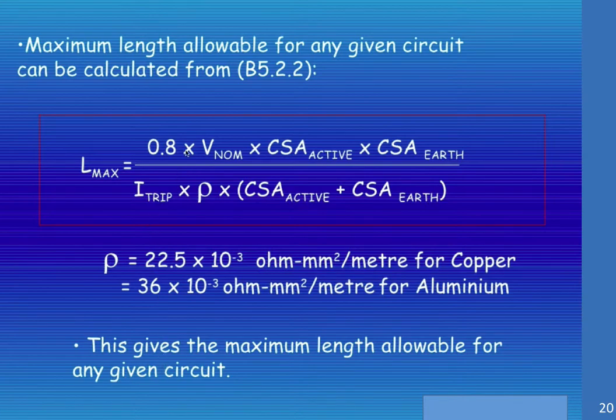We're simply using 80% of nominal voltage, the rated trip current, and by multiplying and adding these cross-sectional areas together and dividing we get a ratio which gives us a maximum length.